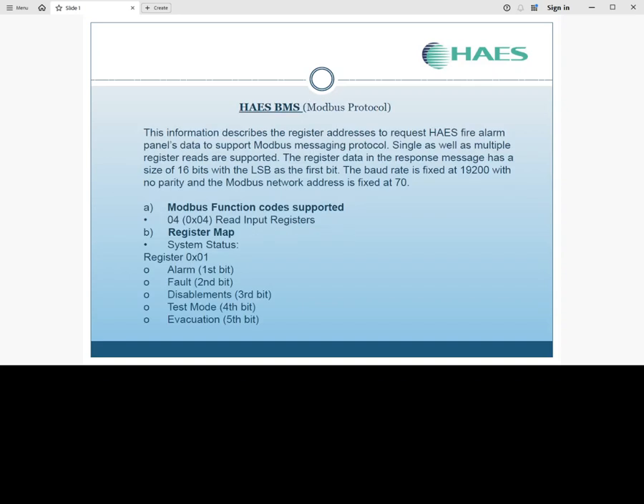The Haes BMS card uses the Modbus protocol. The following information describes the register addresses to request the Haes fire alarm panel's data to support Modbus messaging protocol. Single as well as multiple register reads are supported. The register data in the response message has a size of 16 bits with the LSB as the first bit. The baud rate is fixed at 19200 with no parity, and the Modbus network address is fixed at 70. A. Modbus function code supported. These are 0x04, read input registers.